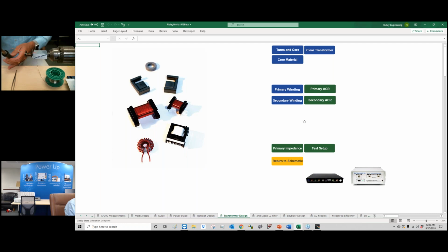It doesn't have a name, but you call up a magnetics company or an insulation company, you say, hey, I want yellow magnetics tape, and they know what you're talking about. But yeah, it's got a proper spec. And when I'm doing design reviews from people, I want to know what the tape is made of, who's making it, the quality and everything else, and the temperature rating of that tape.